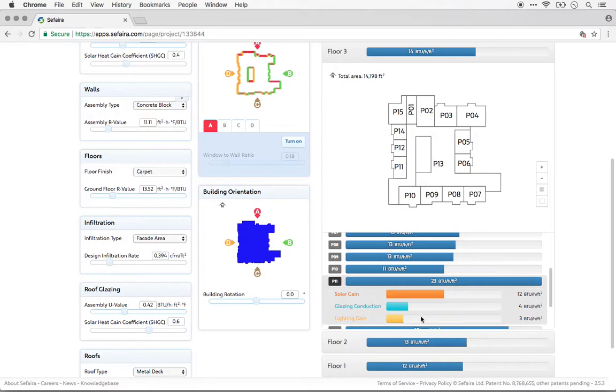and I can see that the largest loads contributing to cooling in this zone are solar gain, glazing conduction, and lighting gain. And so this helps me very quickly diagnose what the problem is. In this case, solar gain is the biggest contributor, so I could look at adding shading to that zone or changing the glazing, perhaps as too much glass, or the properties of that glass.